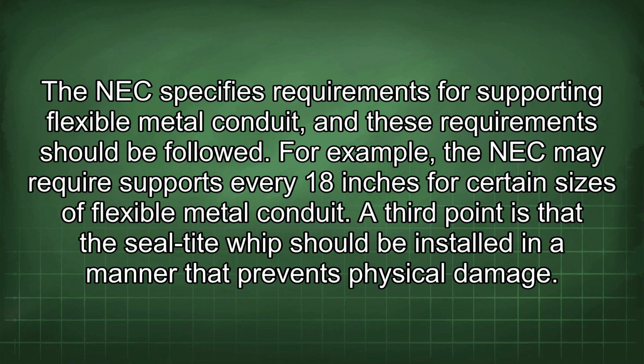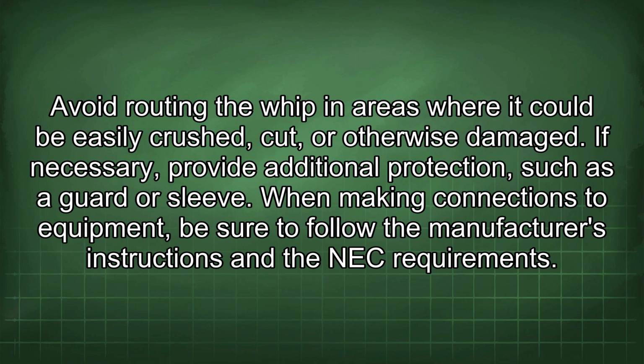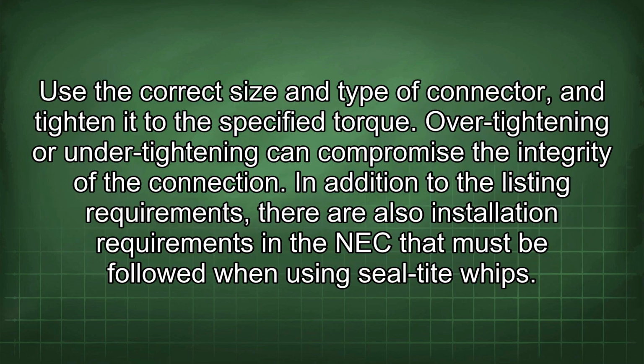A third point is that the Seal-Tite whip should be installed in a manner that prevents physical damage. Avoid routing the whip in areas where it could be easily crushed, cut, or otherwise damaged. If necessary, provide additional protection, such as a guard or sleeve. When making connections to equipment, be sure to follow the manufacturer's instructions and the NEC requirements. Use the correct size and type of connector, and tighten it to the specified torque. Over-tightening or under-tightening can compromise the integrity of the connection.